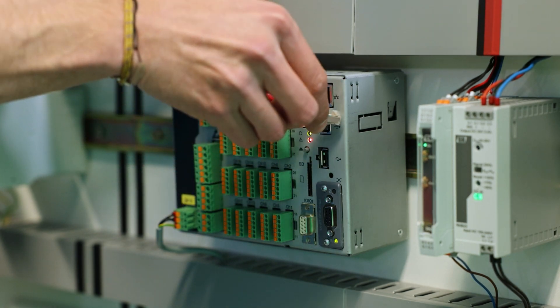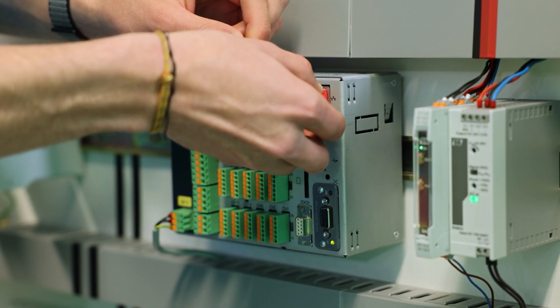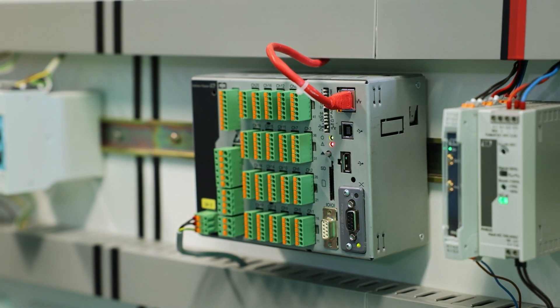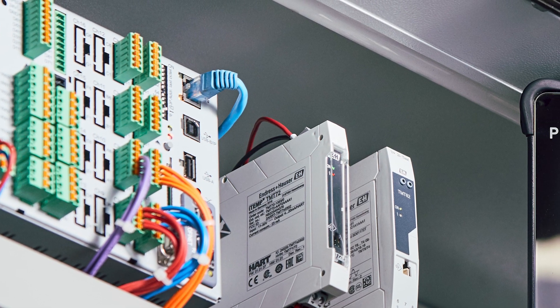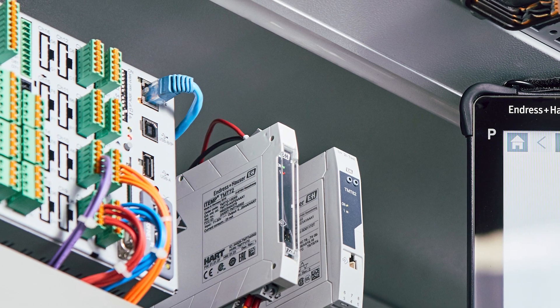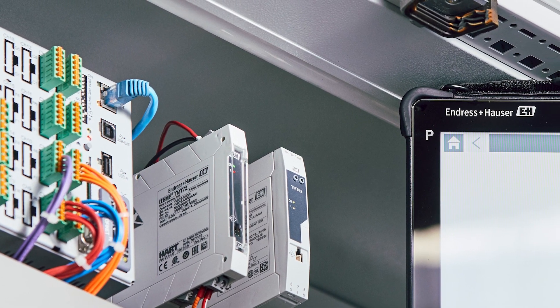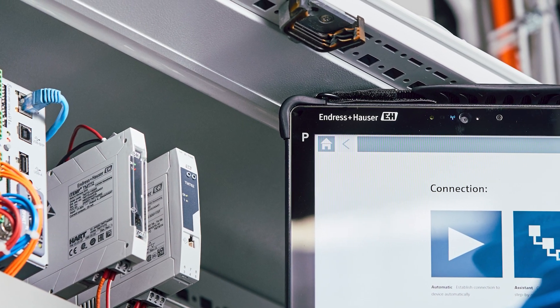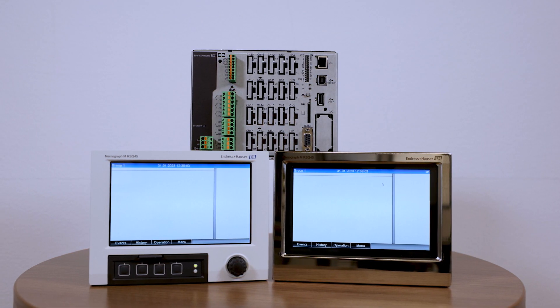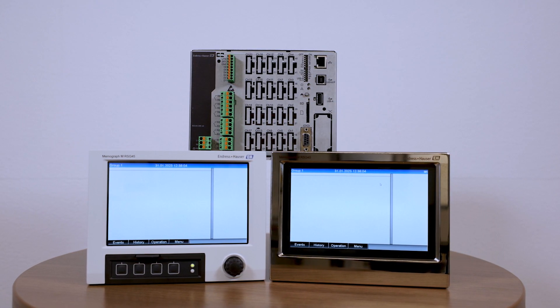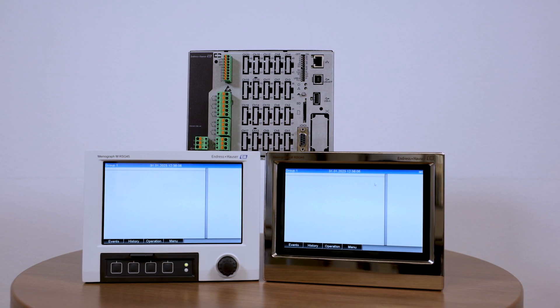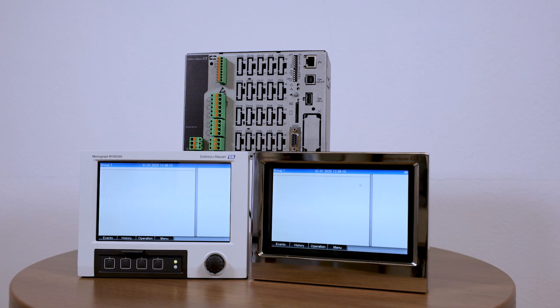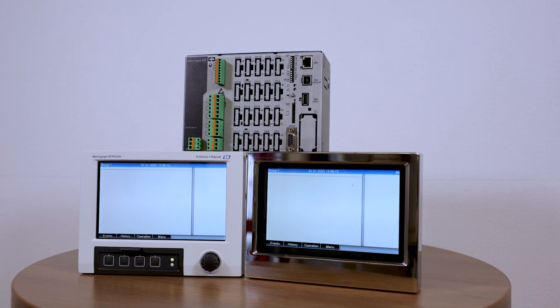The Ethernet interface is a standard feature that comes with every RSG45 regardless of the housing version. This interface brings many advantages such as including the RSG45 in your local network and using the web server or another analysis tool like the OPC server. Additionally, the RSG45 can be configured as a Modbus TCP client or server. This way the Ethernet connection provides an option for a fast integration into your plant.